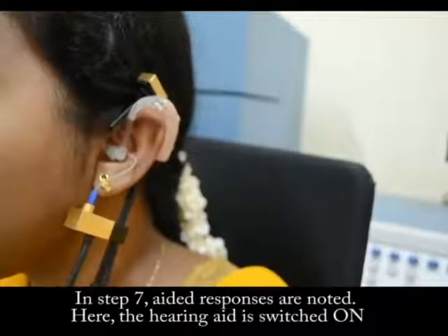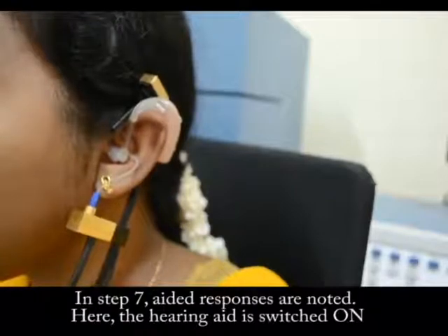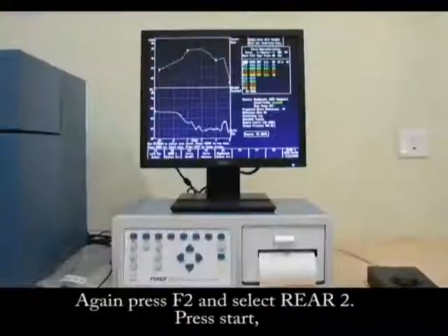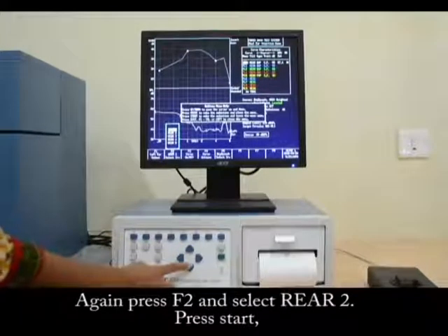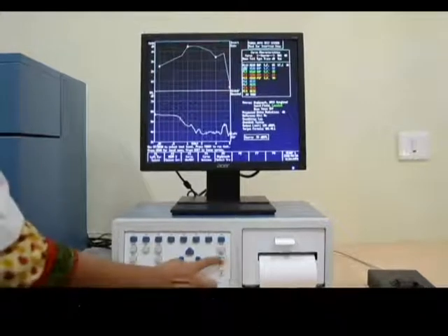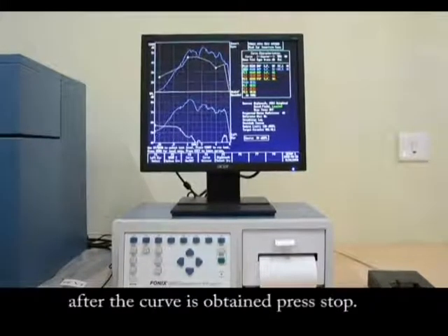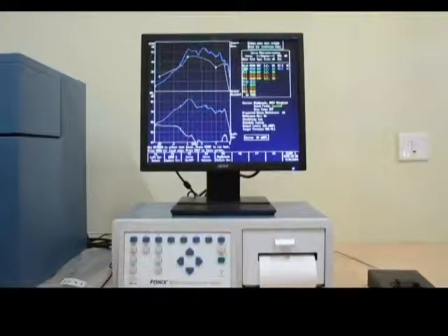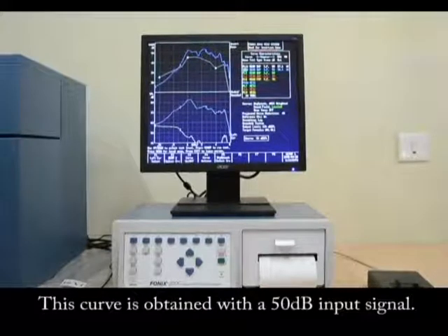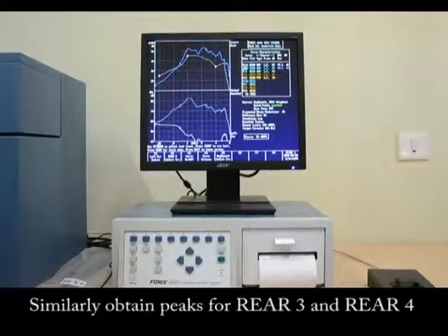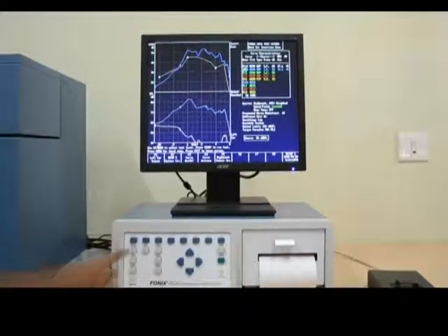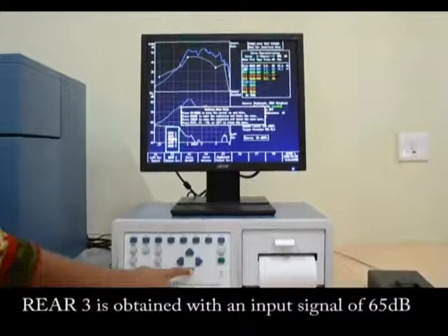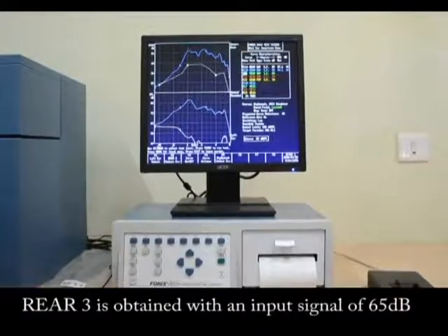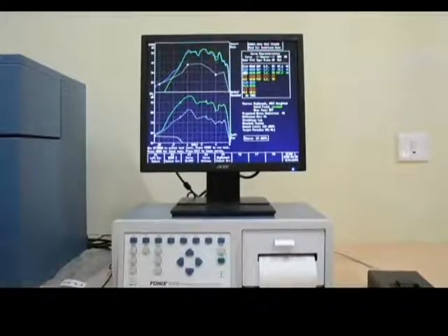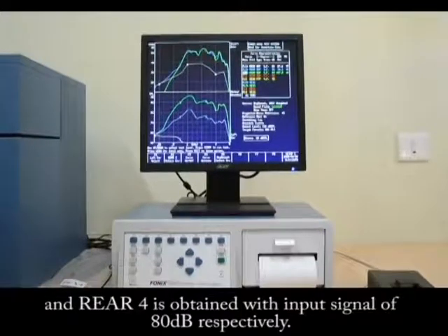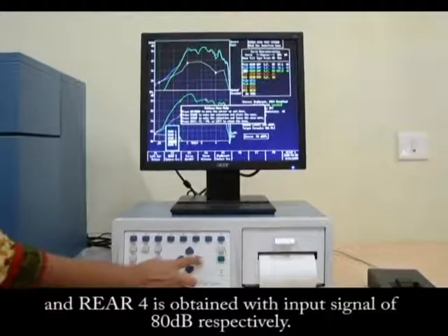In step 7, aided responses are noted. Here, the hearing aid is switched on. Again, press F2 and select REAR2. Press start. After the curve is obtained, press stop. This curve is obtained with a 50 dB input signal. Similarly, obtain curves for REAR3 and REAR4. REAR3 is obtained with an input signal of 65 dB and REAR4 is obtained with an input signal of 80 dB.